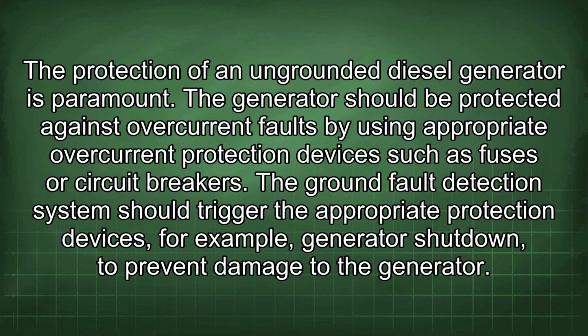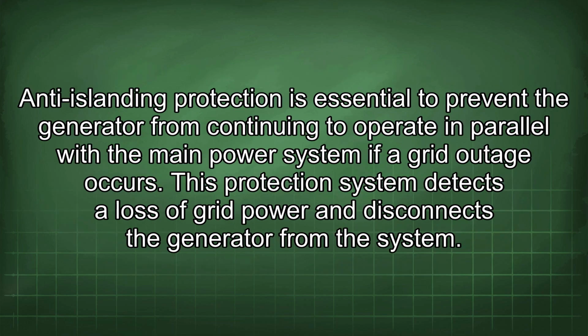Protection of an ungrounded diesel generator is paramount. The generator should be protected against overcurrent faults by using appropriate overcurrent protection devices such as fuses or circuit breakers. The ground fault detection system should trigger the appropriate protection devices, for example, generator shutdown, to prevent damage to the generator. Anti-islanding protection is essential to prevent the generator from continuing to operate in parallel with the main power system if a grid outage occurs. This protection system detects a loss of grid power and disconnects the generator from the system.